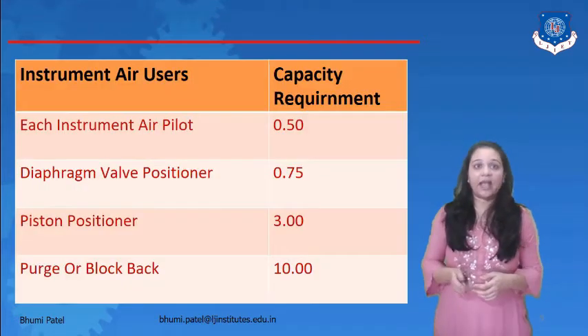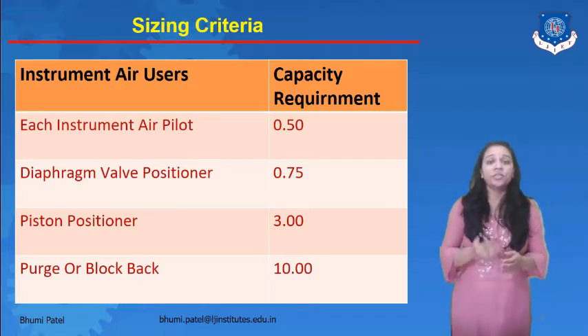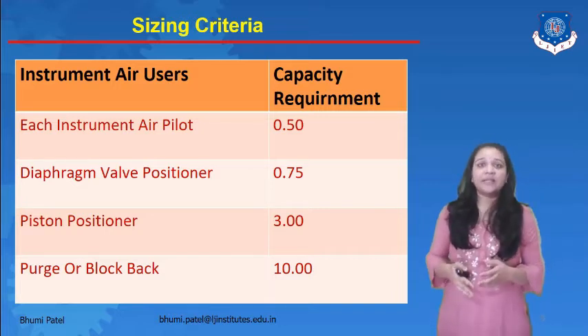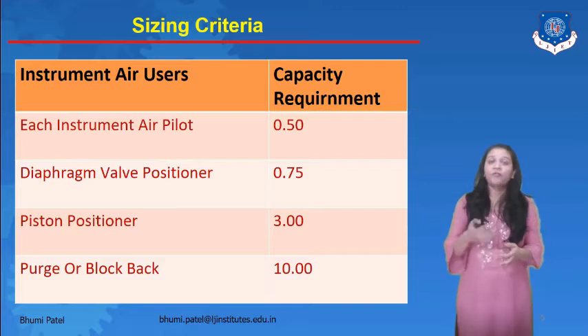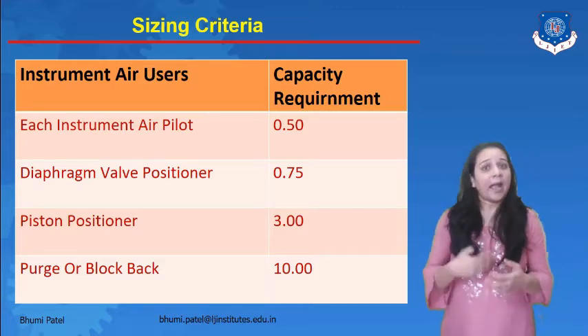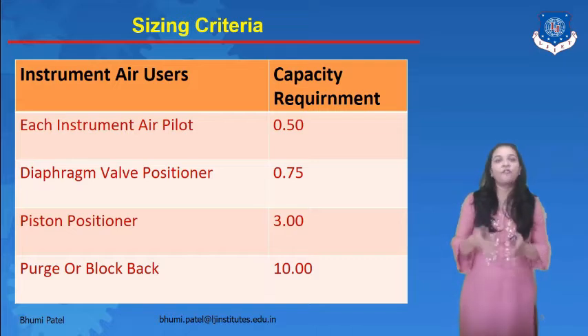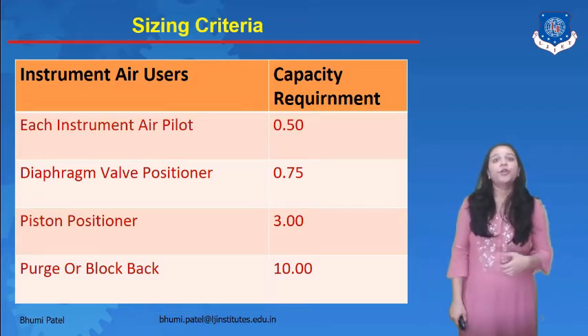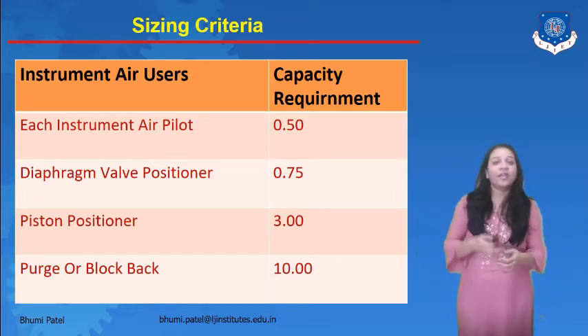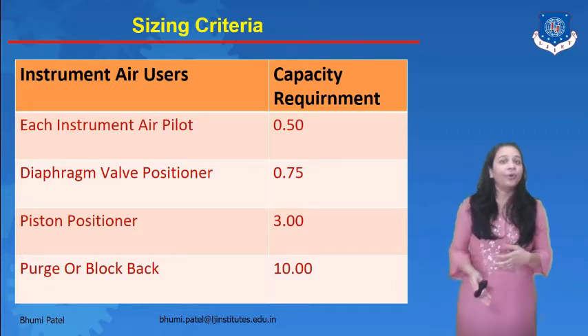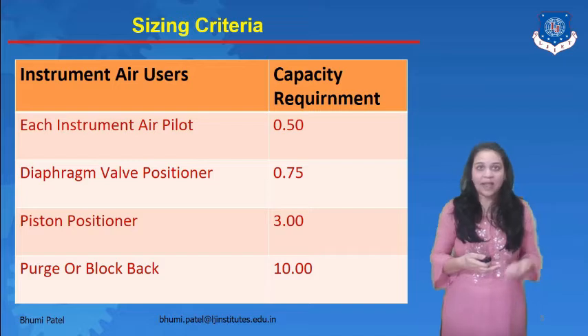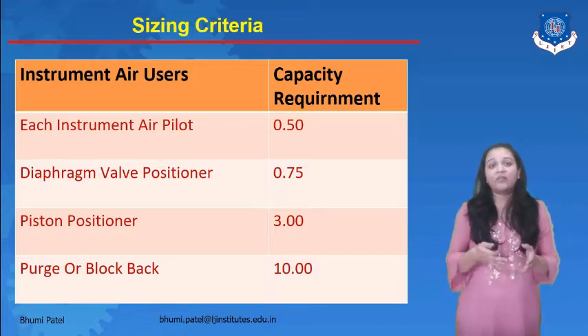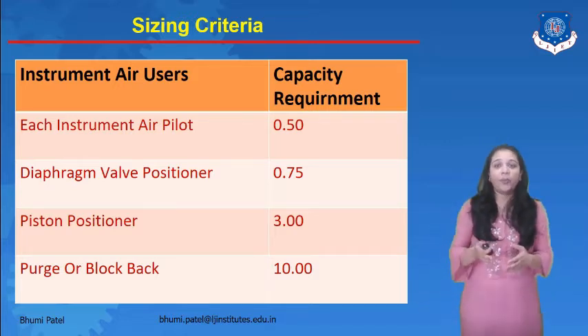The first is the sizing criteria. In the sizing criteria, we use different air users, and for each particular air user there is a different capacity requirement. For example, for an air pilot instrument, the capacity requirement is 0.50. For a diaphragm valve positioner — which decides the position of the control valve — the capacity required is 0.75.